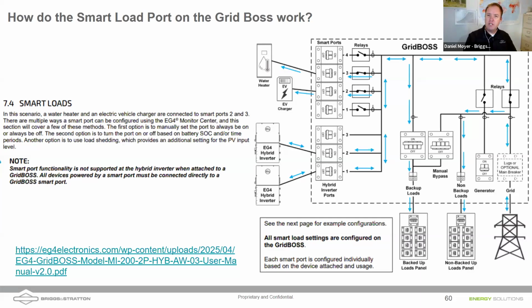One way to get around that is using load shedding capabilities, and the Grid Boss has that built in. These smart load ports have a couple of different logics that we can use. One of the simplest ways is that if the grid is lost, no grid, the smart port will automatically turn off. Grid's there, we're going to allow power to flow through that smart load. But if grid is lost, we're going to shut that load off. It might be a pool pump, a pool heater, something we're not going to need in an outage. We can make them a little smarter than that.